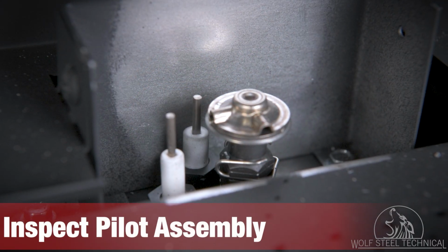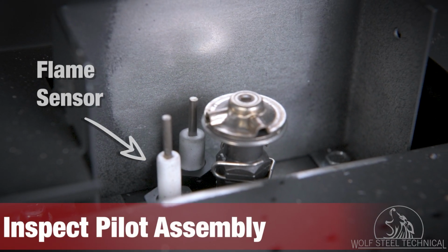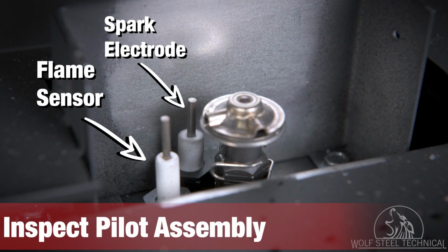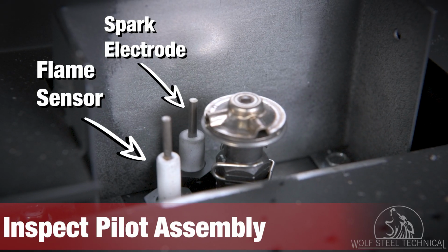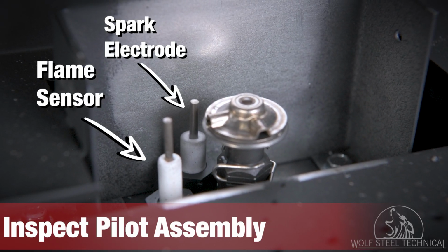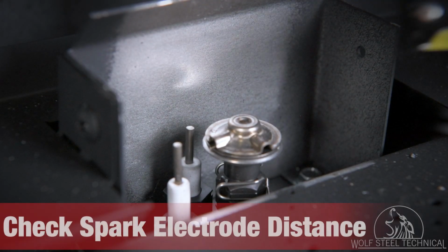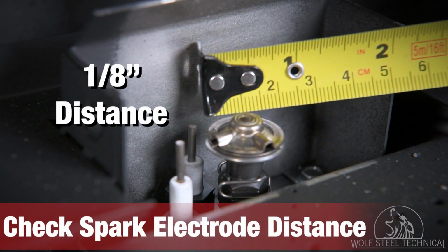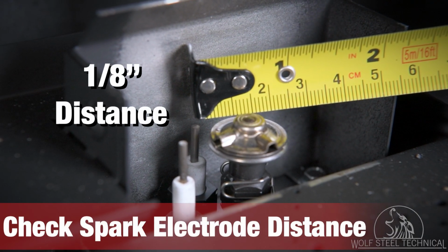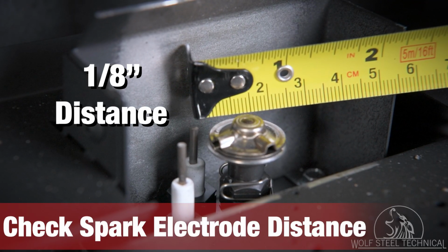Now turn your attention to the pilot assembly. Inspect the flame sensor and spark electrode for cracked or broken ceramic. These must be in good condition for correct operation of the fireplace. Ensure the spark electrode is 1/8 of an inch from the pilot. This ensures the spark will have enough energy to ignite the gas.